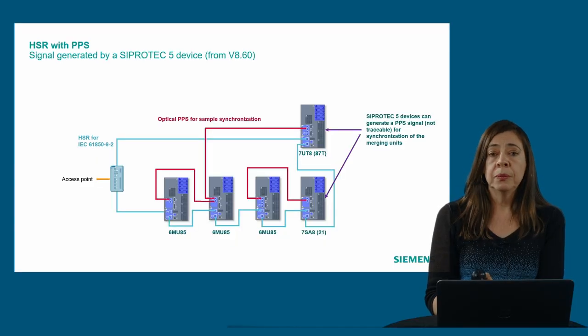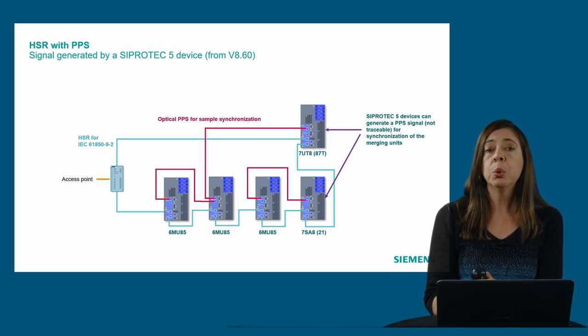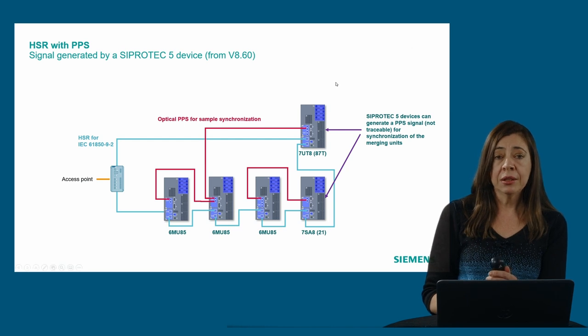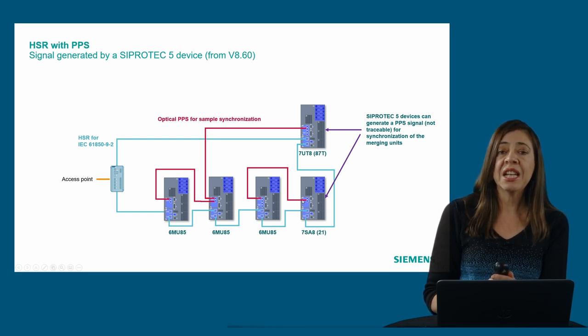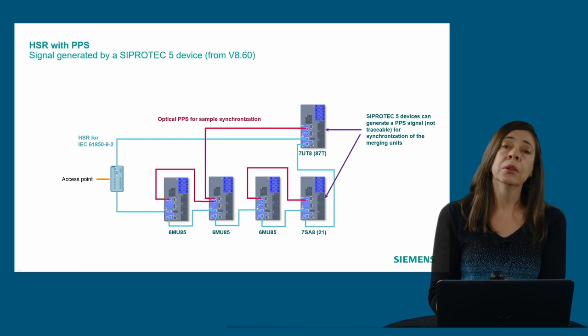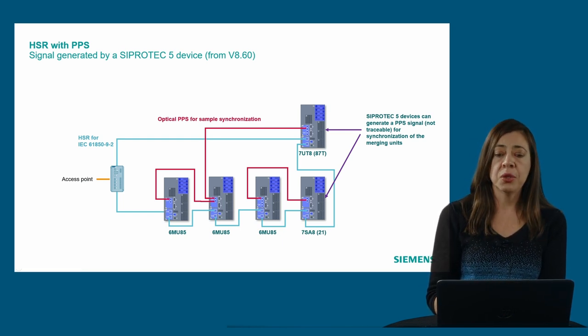In this example, the transformer protection is sending the PPS signal to the 2 merging units required for the algorithm. So we have the output of the protection device connected to the first merging unit. This signal is mirrored and connected to the second merging unit. In this case, also the distance protection is generating the PPS pulse for its own merging unit. In this implementation, then you don't need to use external synchronization devices.